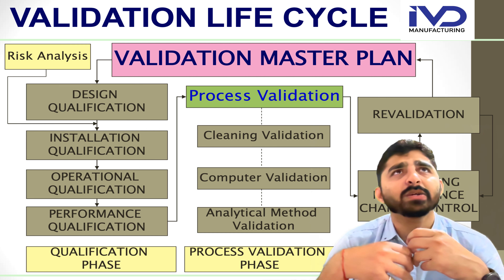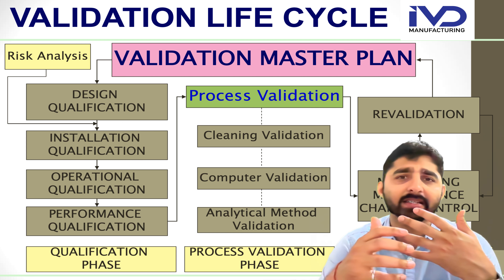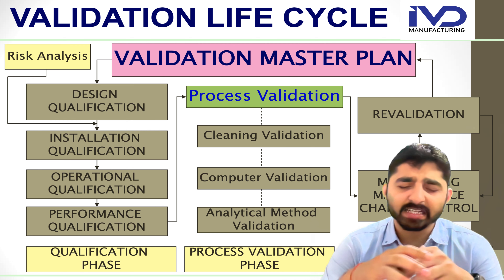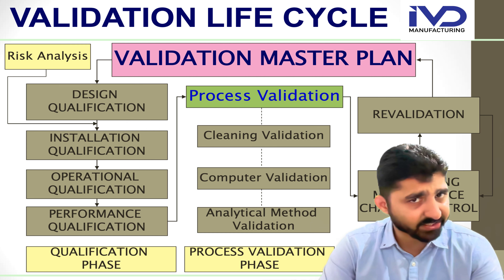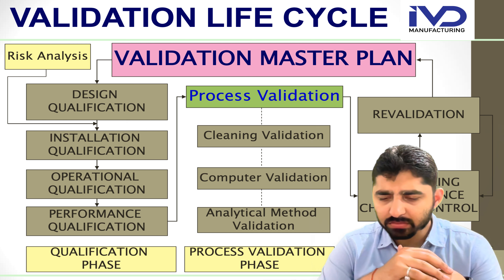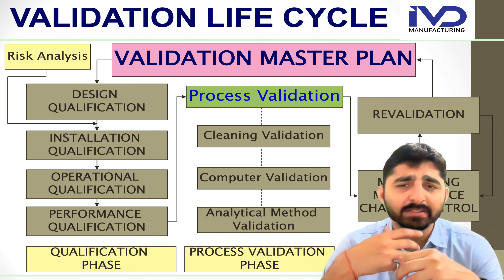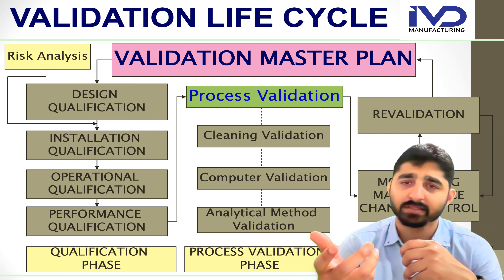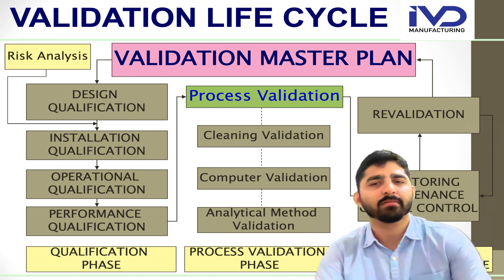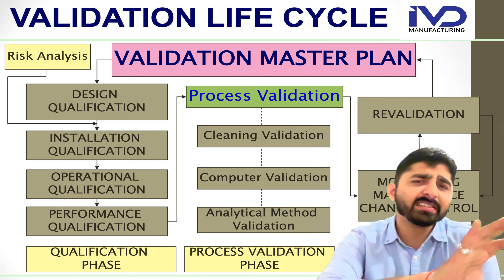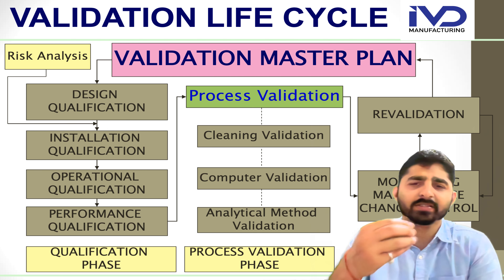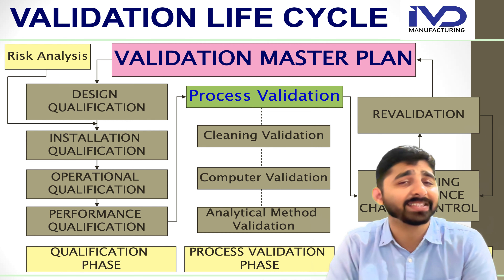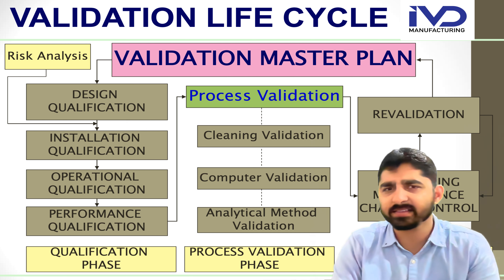For example, if I have a clean room and I am maintaining ISO Class 8 for manufacturing a particular product, I need to revalidate my clean room after 6 months or 12 months, depending on usage and criticality. This is called revalidation. The entire process — qualification, process validation, and maintenance phases — must be monitored and governed by the change control systems.